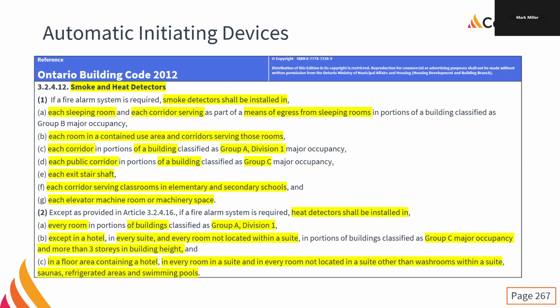But smoke detectors have to be installed in certain places, and this is whether or not a building is sprinklered. Sprinkler heads are fire detectors. They function under the exact same principles as fixed heat detectors. They do not detect smoke. So we cannot replace smoke detectors with sprinkler heads. Does not work. So even when we have a sprinkler system, we have to put in smoke detectors.